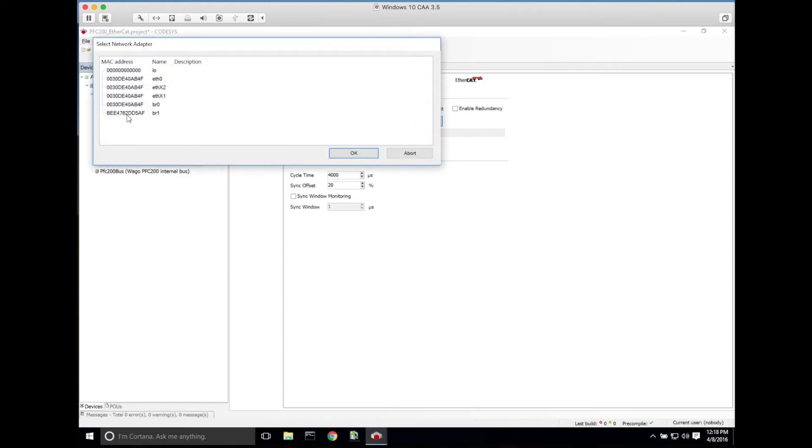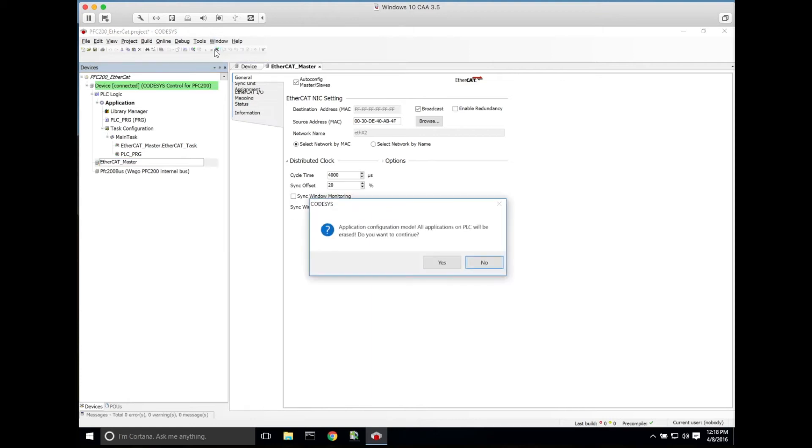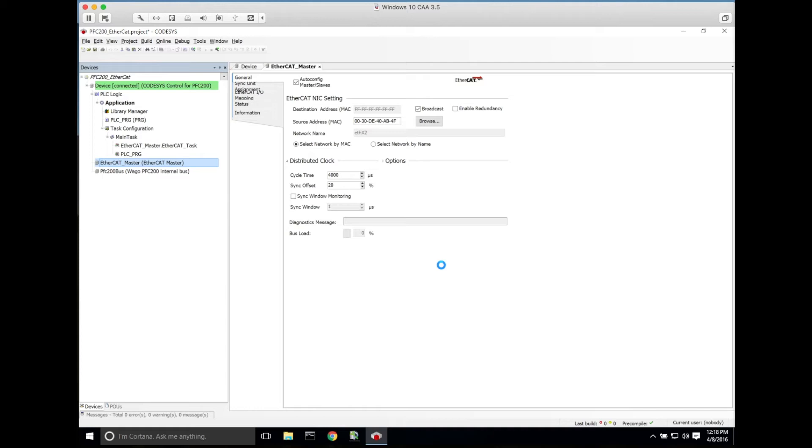We'll need to tag this to the proper port, so you'll have to pay attention to which port you plug your EtherCAT coupler into. EtherCAT does require a dedicated port. Once we've done that, we will select the EtherCAT master and go to online configuration.